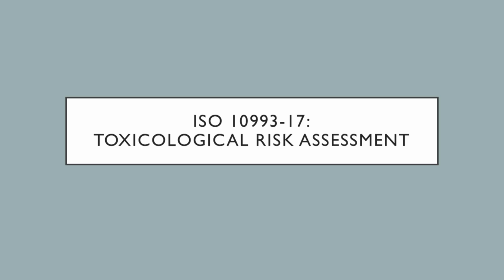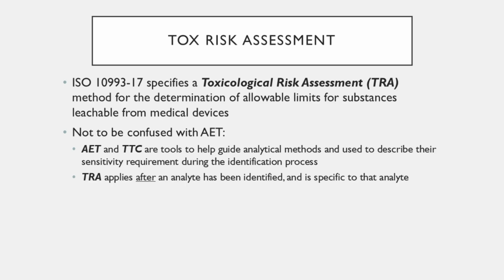No one cares in a vacuum how much of a particular material is present or gets extracted from a material. We only care about the toxicological risk that accompanies that particular material. So now we're going to shift to the -17 ISO standard that governs and discusses the TRA, or the Toxicological Risk Assessment. The definition of the toxicological risk assessment is that it's a method for determining the allowable limits of substances that are leached from your specific medical device.